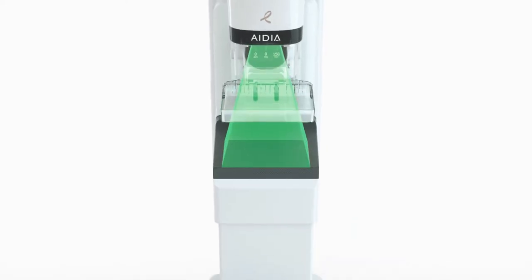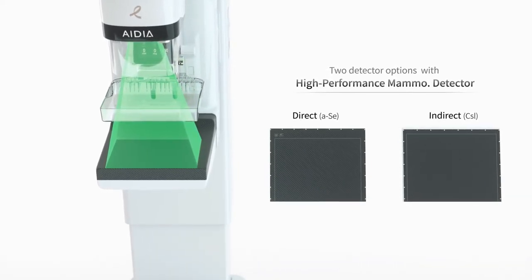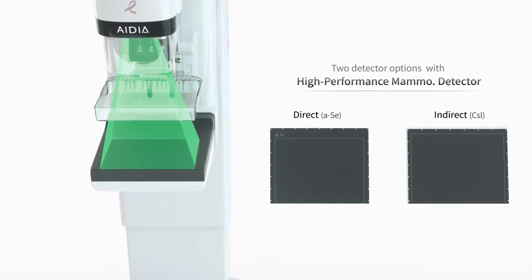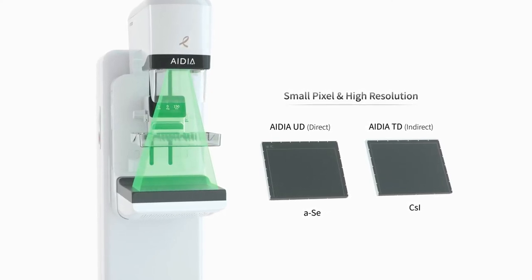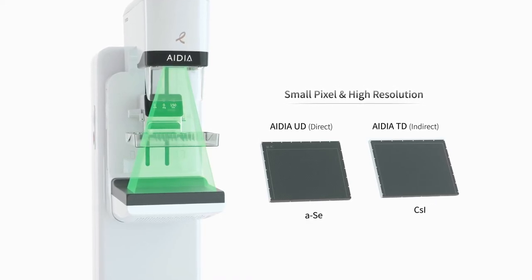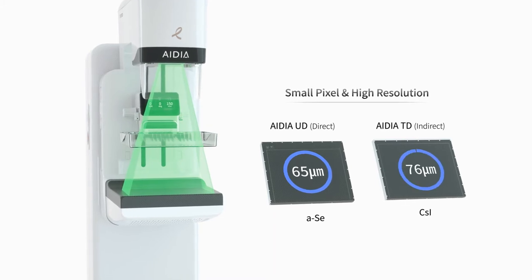AIDIA is available in two detector options: AIDIA UD, direct type selenium technology, and AIDIA TD, indirect type CsI technology. Both UD and TD options guarantee the highest resolution images with the smallest pixel size among all currently available digital mammography systems, with 65 micron and 76 micron pixel sizes.